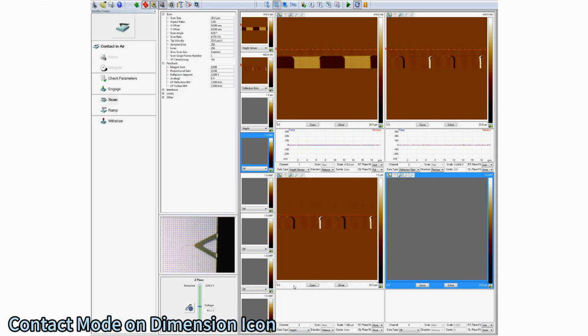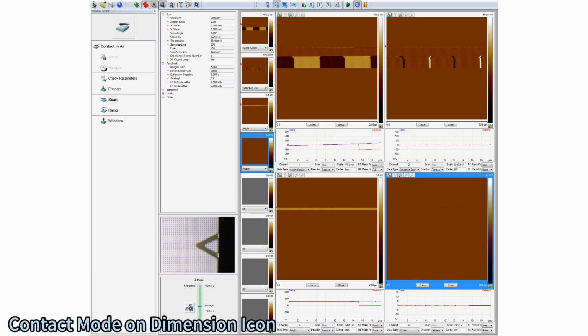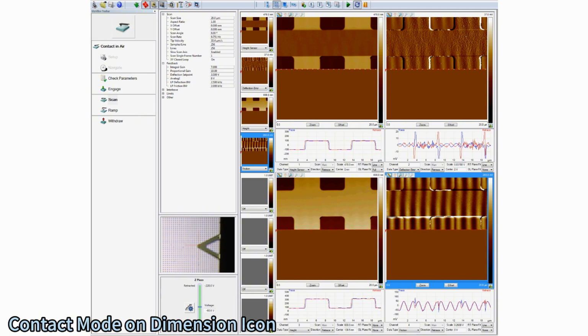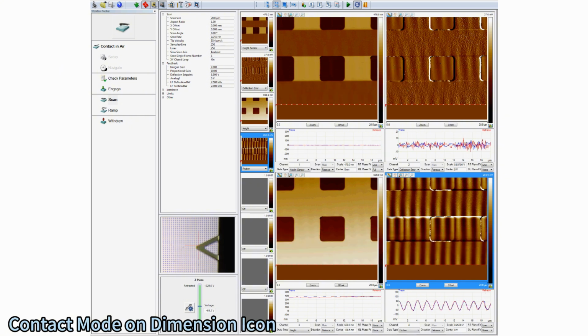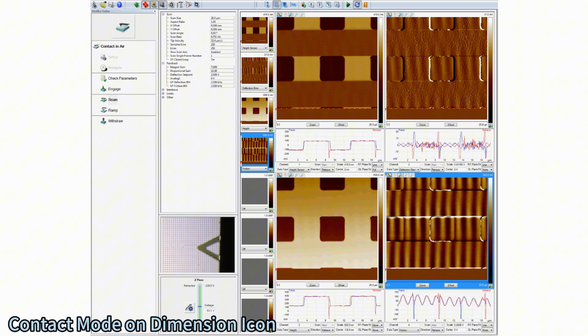Additional channels may be opened to display deflection error, which reflects the variation between the current probe deflection value and the set point value, or friction, that displays the variation in the tilt of the cantilever from left to right. While a scan is collecting, the user may choose to adjust parameters such as speed, gain, or set point if improvements in the image are necessary.